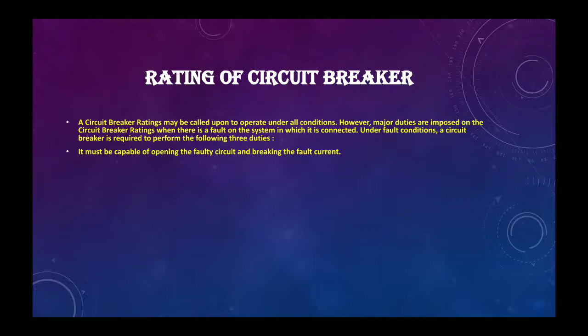Number one, it must be capable of opening the faulty circuit and breaking the fault current. Number two, it must be capable of being closed on to a fault. And the third one is it must be capable of carrying fault current for a short time while another circuit breaker in series is clearing the fault. So that is the main duty of a circuit breaker.